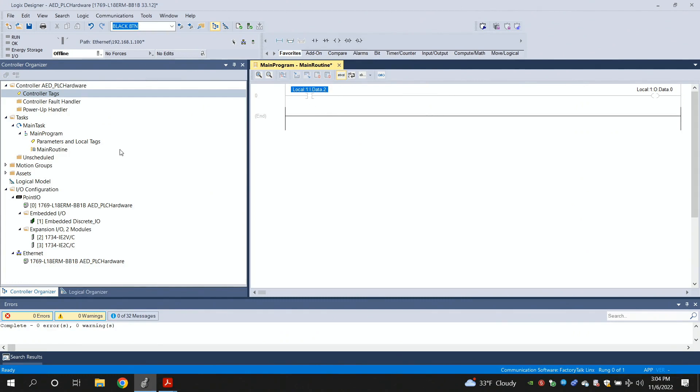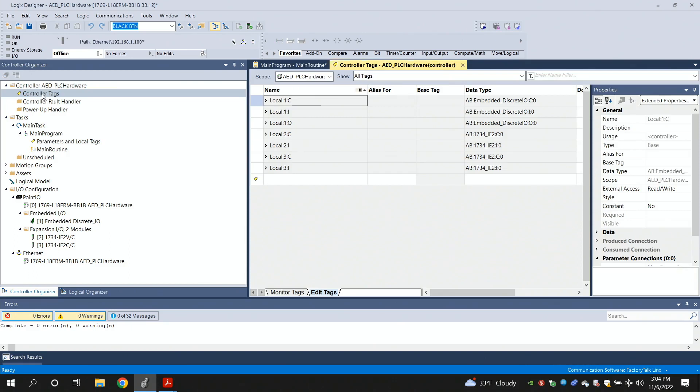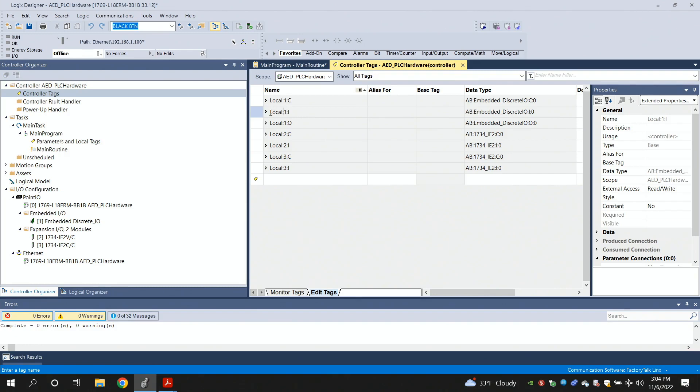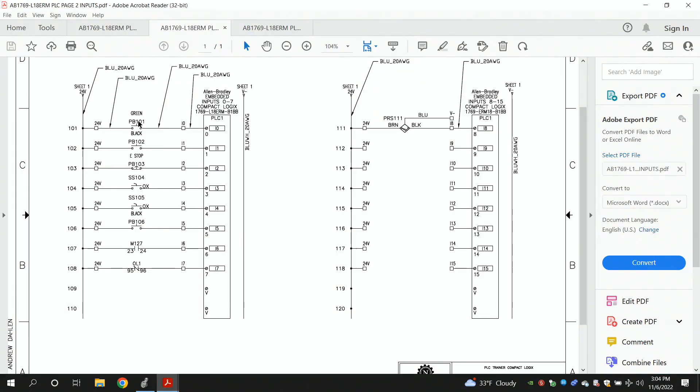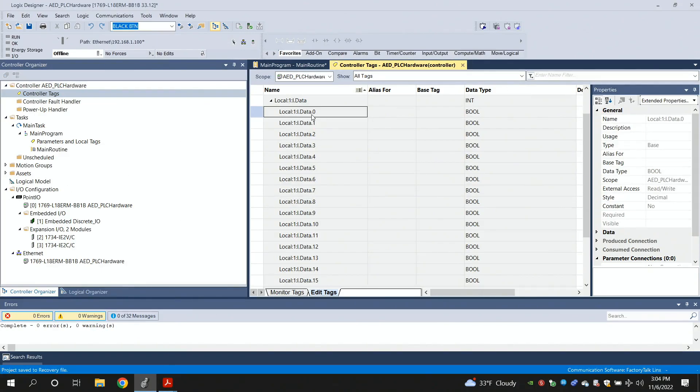Let's get into a tab over here that's called controller tags. If I were to click on our controller tags, that's where I can see a list of all of the inputs and outputs for this controller, and some of the expansion modules. The I1's that we were talking about are located over here, and here's the I1 data. This basically, data 0 would be input 0, as we would call it from our schematics. That would be input 0, this green push button, I0, that's what's physically wired up to it. The selector switch would be on I3, and etc. They show up here under our controller tags, and that's how they reference them.